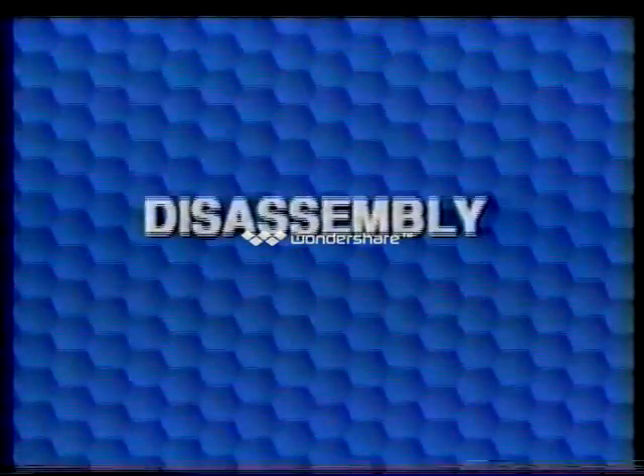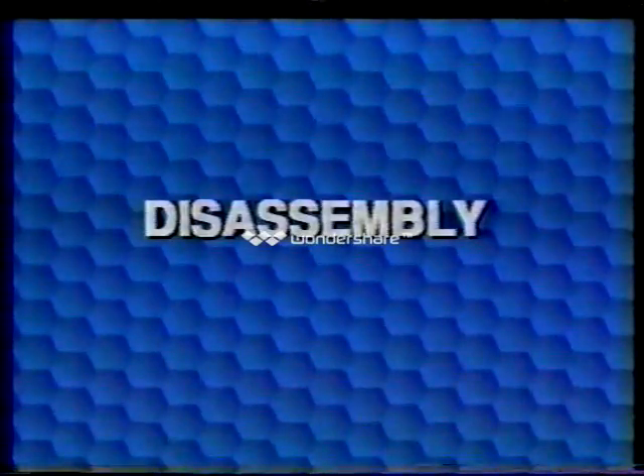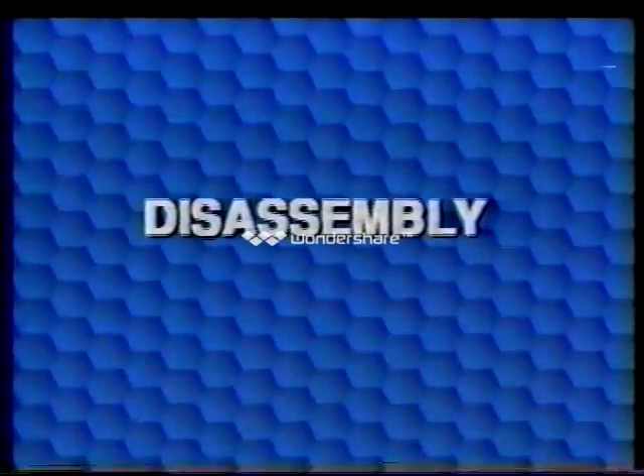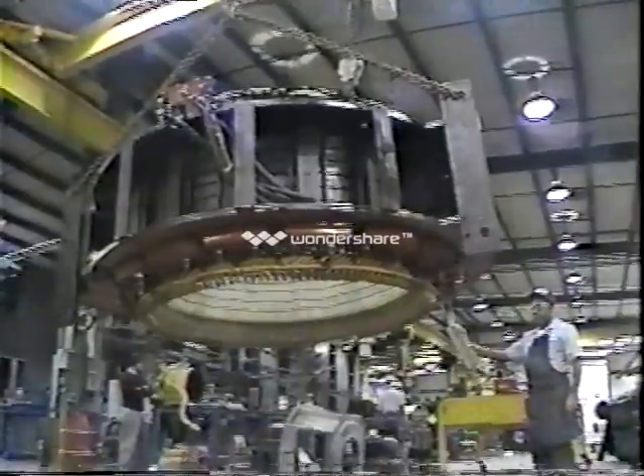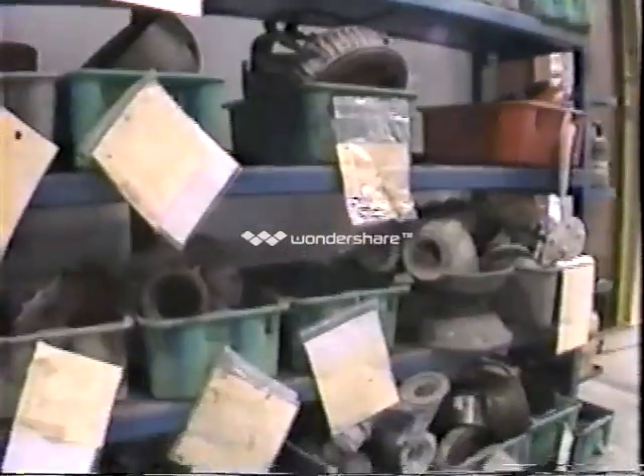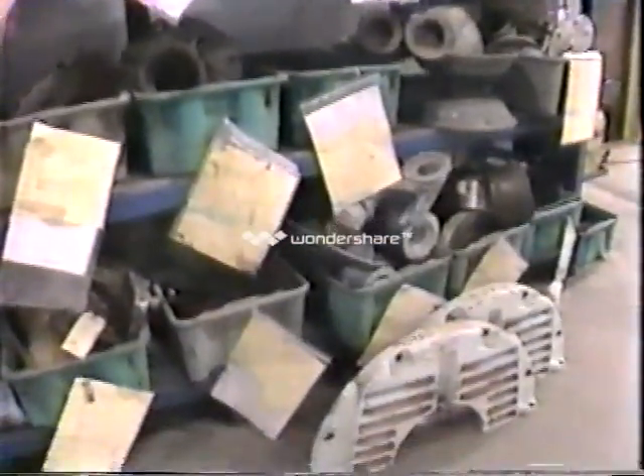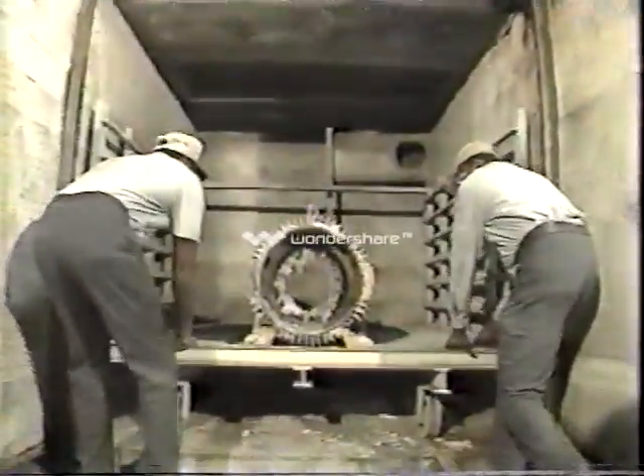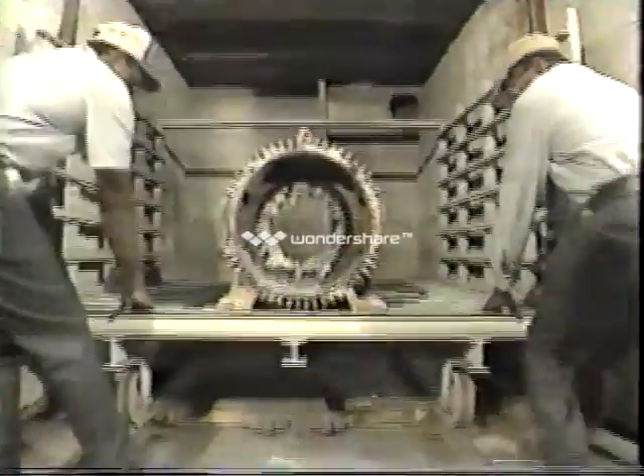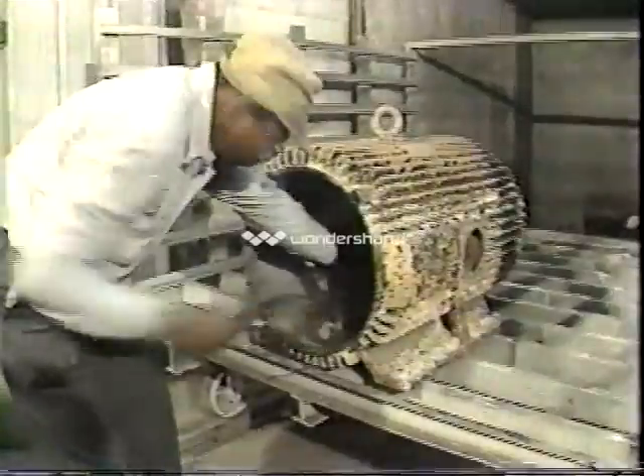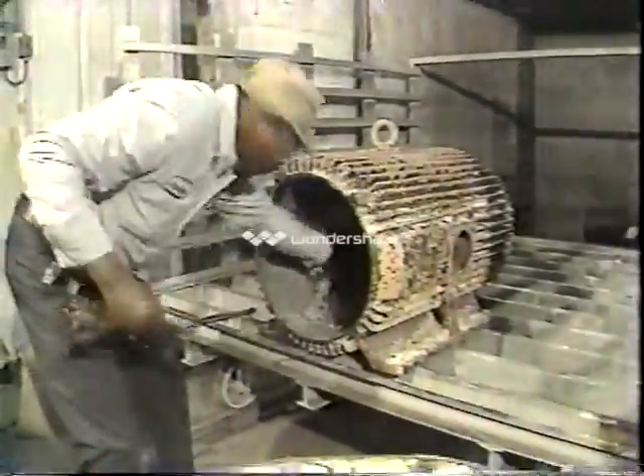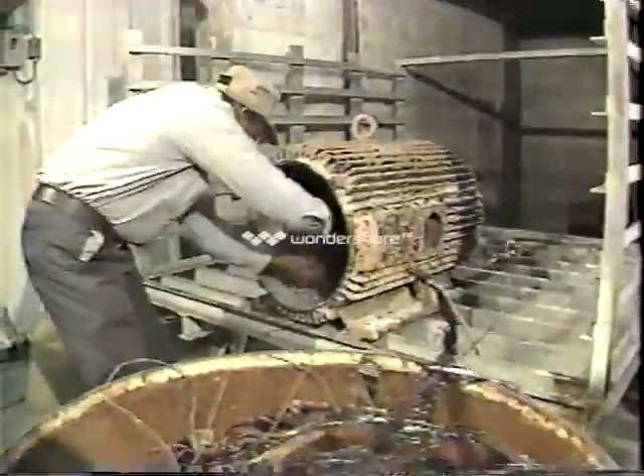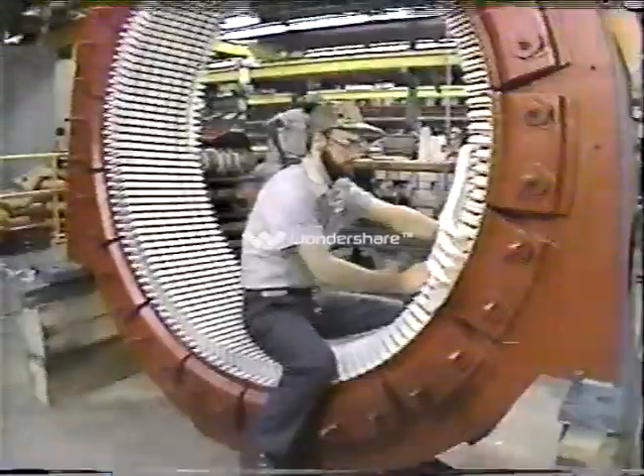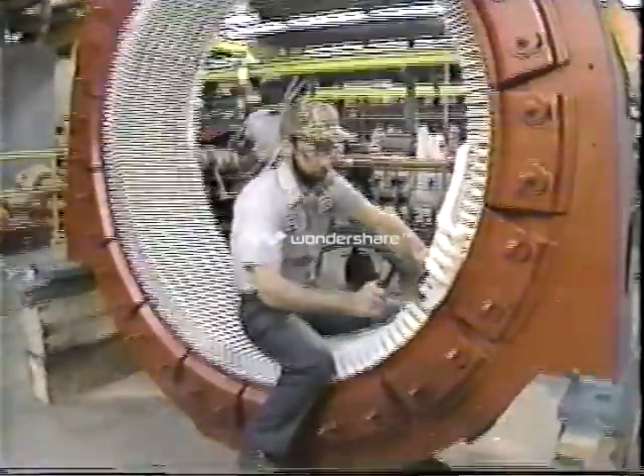One of the first things that happens to your equipment after it arrives at Ingleside Electric is the disassembly process. We carefully dismantle and analyze the equipment, cataloging every part as it's removed. If a motor is to be rewound, we place the stator of the motor in our temperature-controlled burnout oven in order to break down the hardened resins that contain the old winding that is then removed and recycled. After the burnout oven, the stator is cleaned and sent to our motor rewinding department.